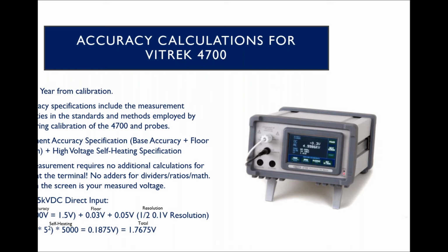The direct measurement does not require any additional calculations for the accuracy at the terminal. You still need to take into consideration all of the other sources of error that might be external, but there's no additional devices that are needed when you're doing a measurement with a 4700. So there's no other devices to add to your overall uncertainty in that manner. So what's on your screen is your measured voltage, and there's a brief example down below on exactly how to perform that calculation, and you can see some of the accuracies that we can achieve there.